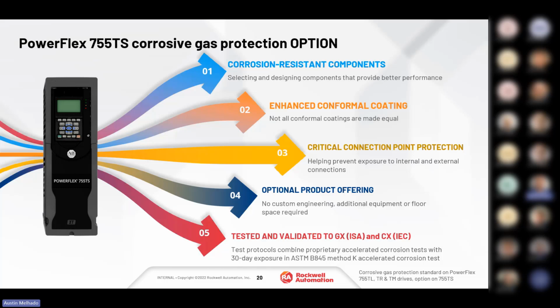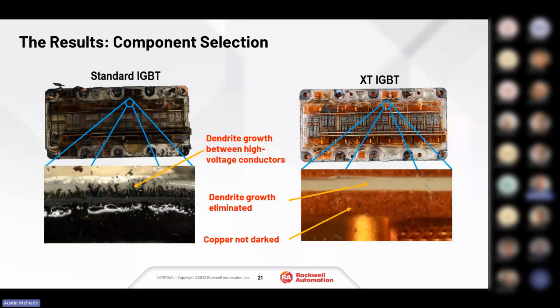Last year I went to Mequon, and I was able to visit the state-of-the-art mixed gas test chambers. Rockwell has this chamber where they put their components through an accelerated rate to replicate long-term exposure. And we can see the difference between standard IGBT conformal coating and XT conformal coating on IGBTs, which will be in this next slide right here. So the standard IGBTs, again, have conformal coating, but not rated conformal coating for long-term exposure.